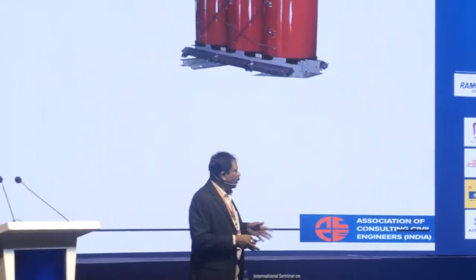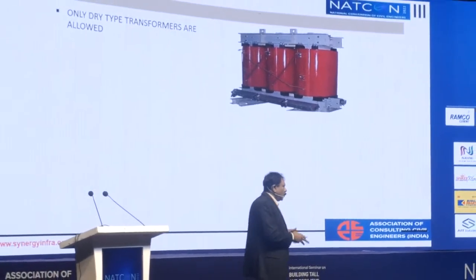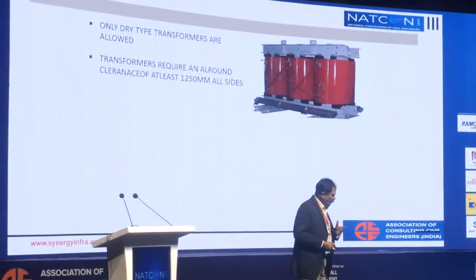and how do we protect them. So when we talk about inside the buildings, naturally there should be no oil because it's prone to fires. So it has to be only a dry type transformer, especially for the buildings. The Indian electricity rules, at present called CEA Safety Guidelines 2023, say that for any building, industries and all, oil cooled transformers are still allowed inside a building, but for high-rise buildings, only dry type transformers have to be used at any level.